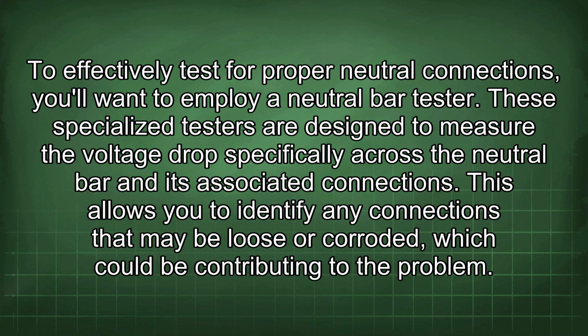To effectively test for proper neutral connections, you'll want to employ a neutral bar tester. These specialized testers are designed to measure the voltage drop specifically across the neutral bar and its associated connections. This allows you to identify any connections that may be loose or corroded, which could be contributing to the problem.